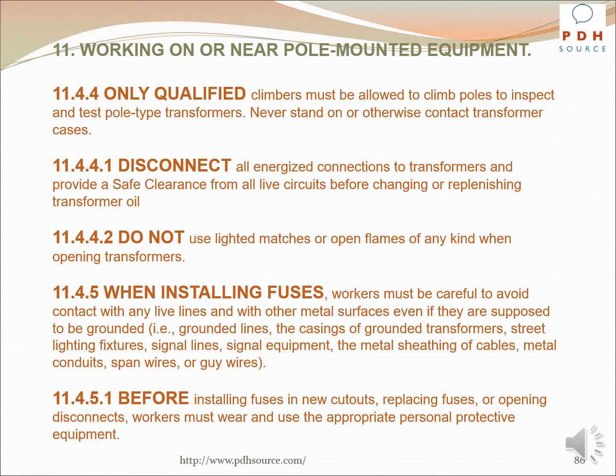When installing fuses, workers must be careful to avoid contact with any live lines and with other metal surfaces even if they are supposed to be grounded, i.e. grounded lines, the casings of grounded transformers, street lighting fixtures, signal lines, signal equipment, the metal sheathing of cables, metal conduits, span wires, or guy wires. Before installing fuses in new cutouts, replace fuses or opening disconnects, workers must wear and use the appropriate personal protective equipment.